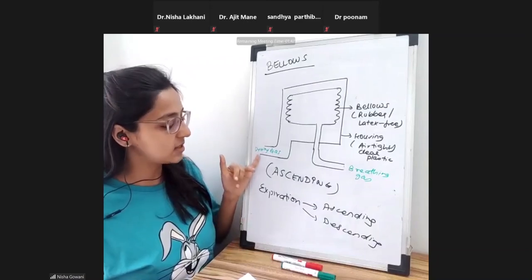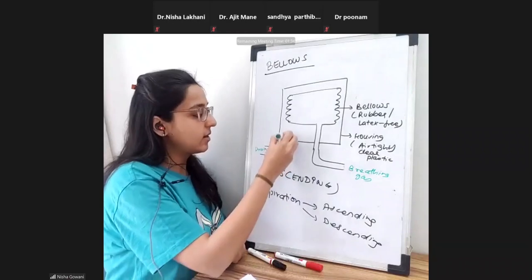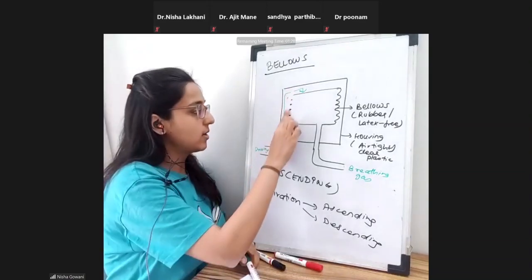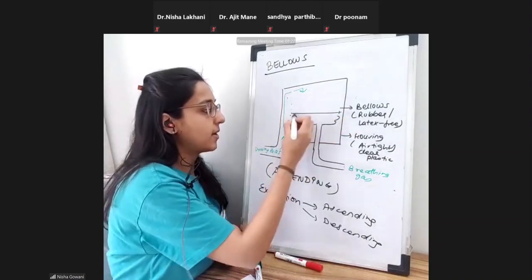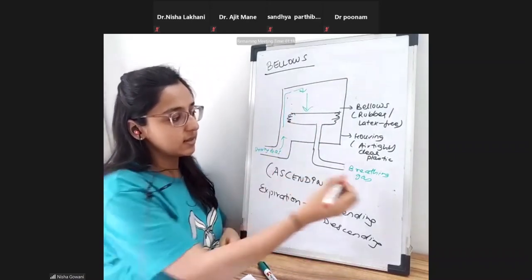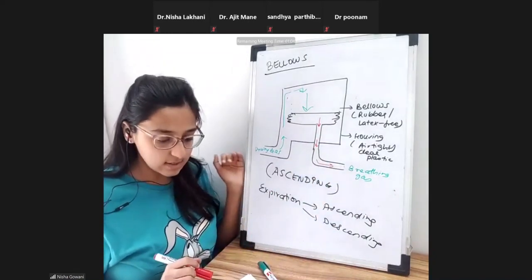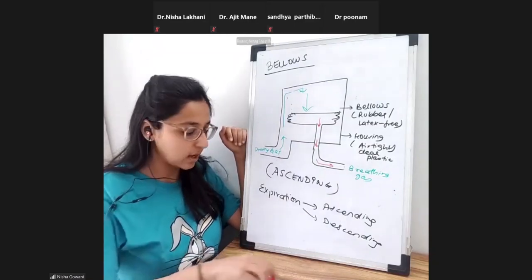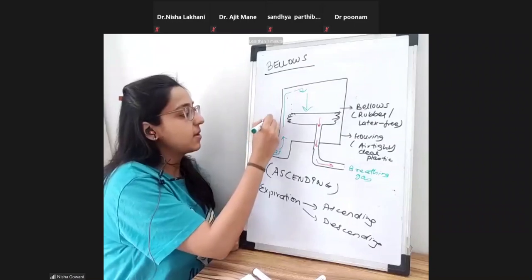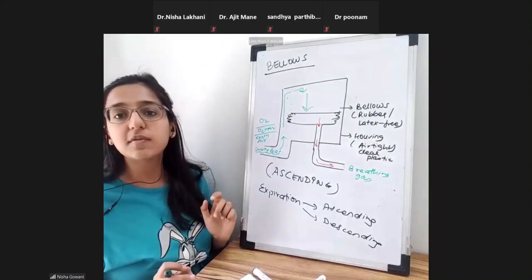What is the driving gas, and what is its role? This gas enters into the bellows housing where the bellows is placed. The job of this driving gas is to compress the bellows. During inspiration, the driving gas presses the bellows, which gets compressed, and the breathing gas inside the bellows — the gas the patient will receive — leaves the bellows and goes towards the patient circuit. The driving gas can be oxygen, oxygen plus air, or room air.